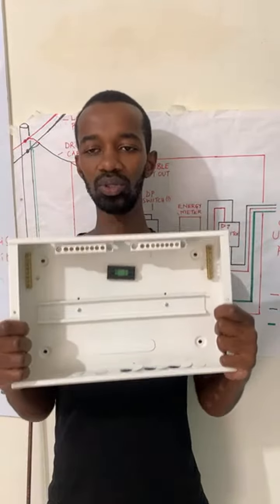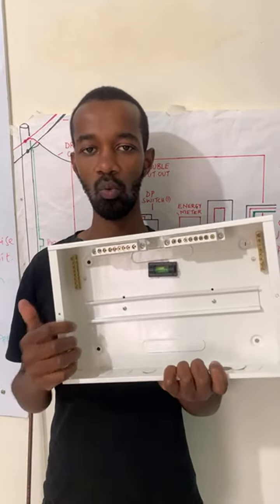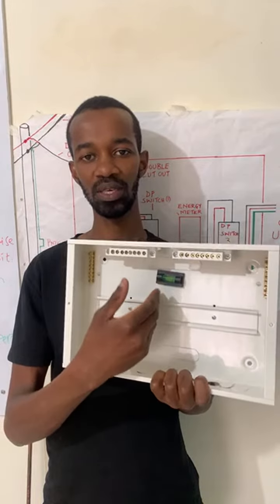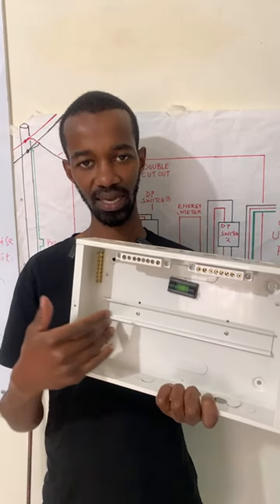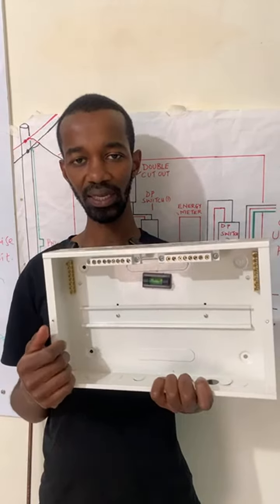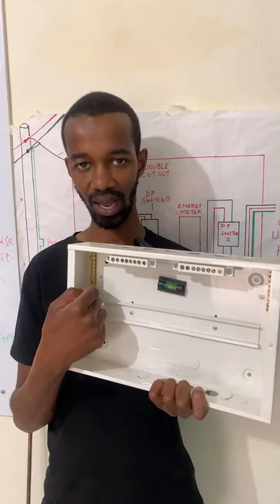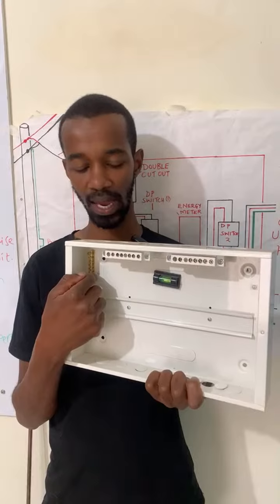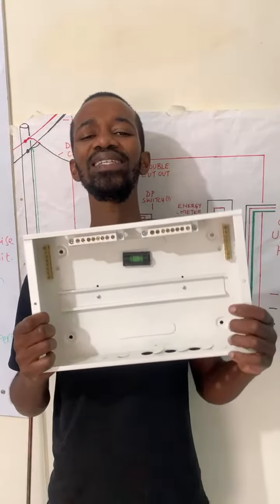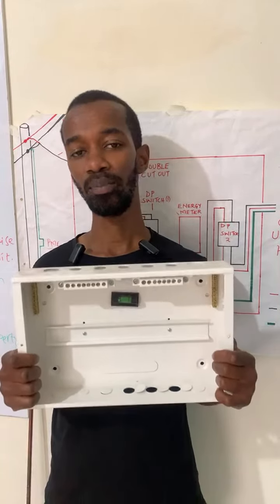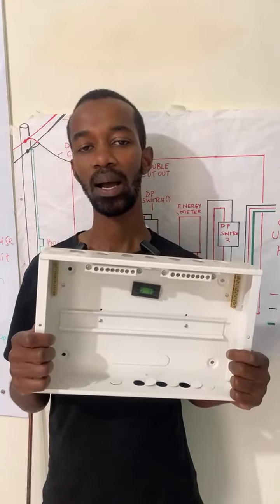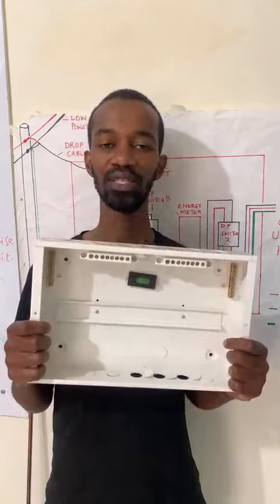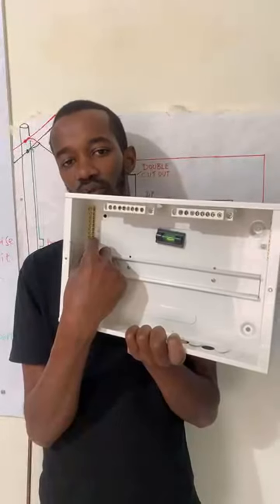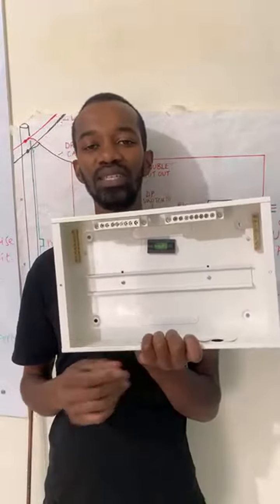So if we are talking about this as our consumer unit, once you connect the phase connection from these MCBs that are normally placed at this DIN rail here, you will definitely have to connect each and every earthing point at this earth bar. And while doing that, you make sure that you do a tight connection. There is also another mistake that people make when they are stripping the copper, the insulation. They leave some insulation so that when they are screwing this part here to that wire, they screw on the insulation and not the copper wire. That is a grave mistake because that circuit is not yet earthed.